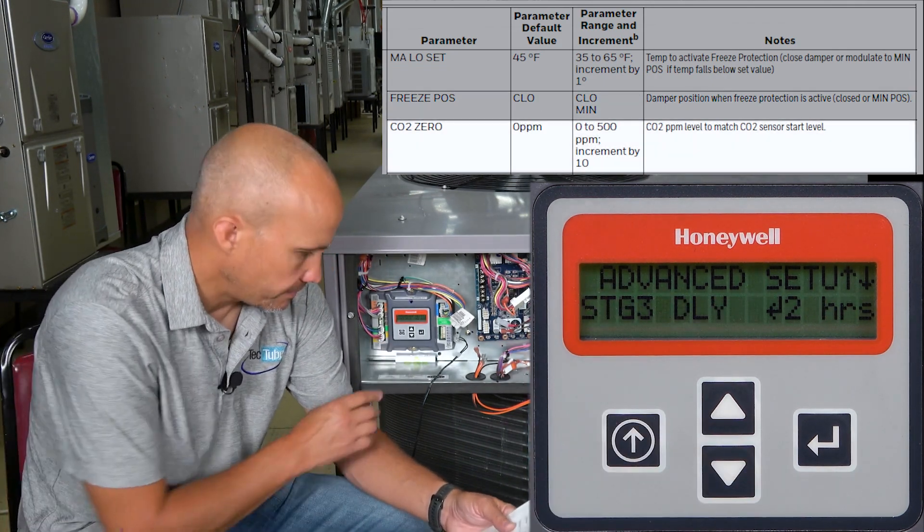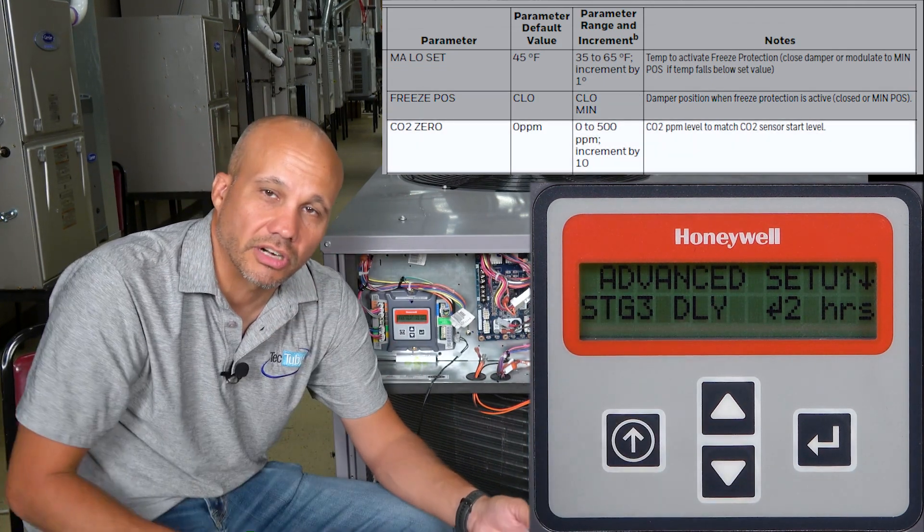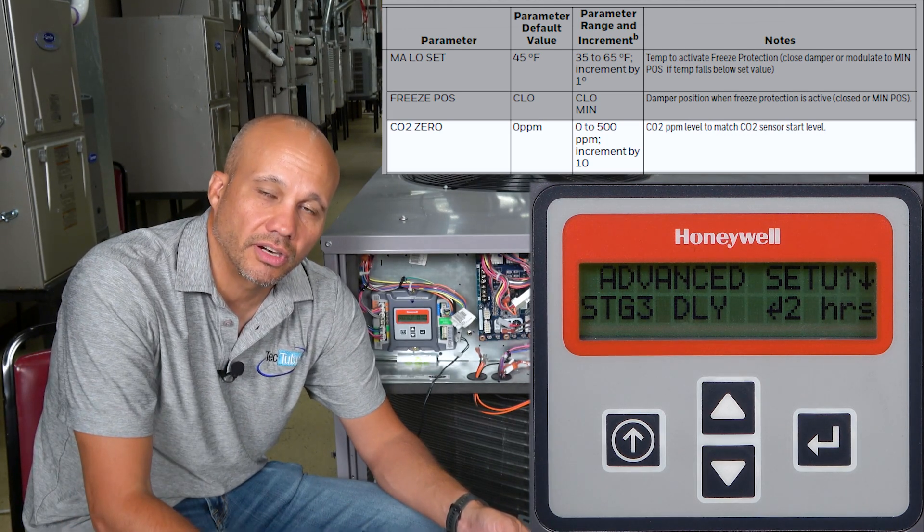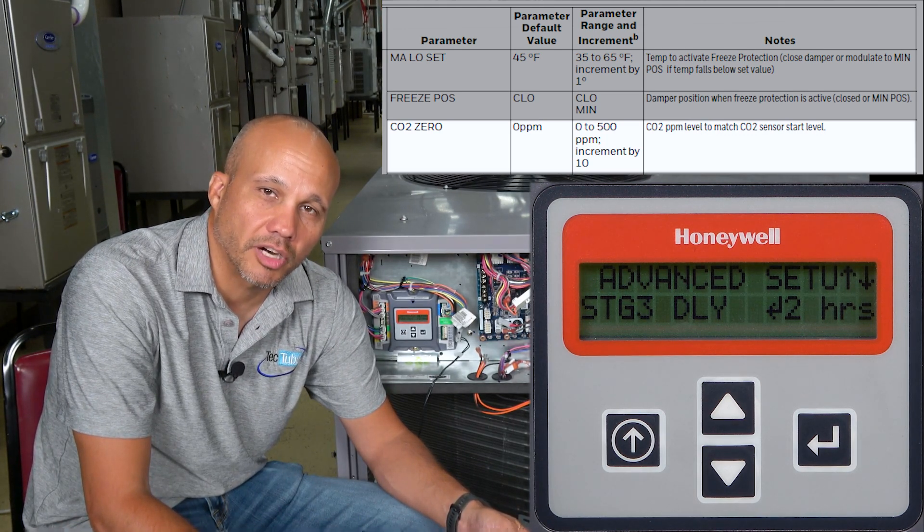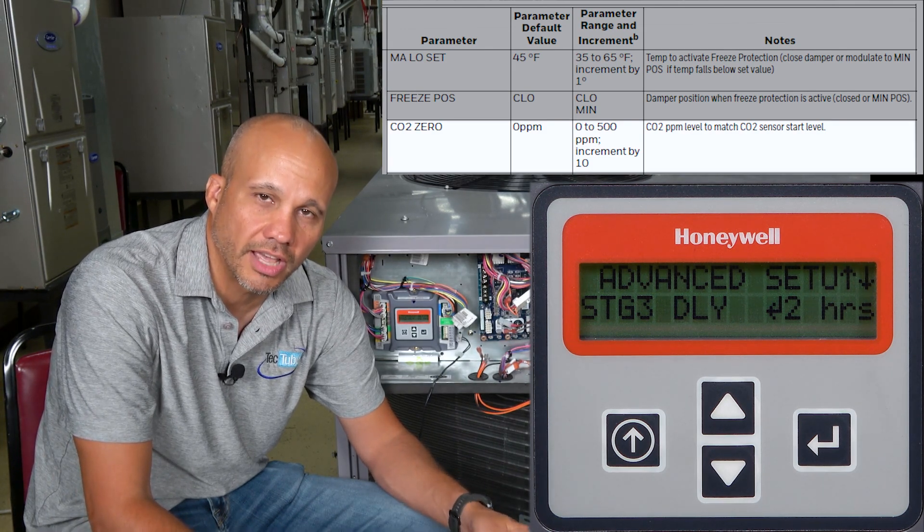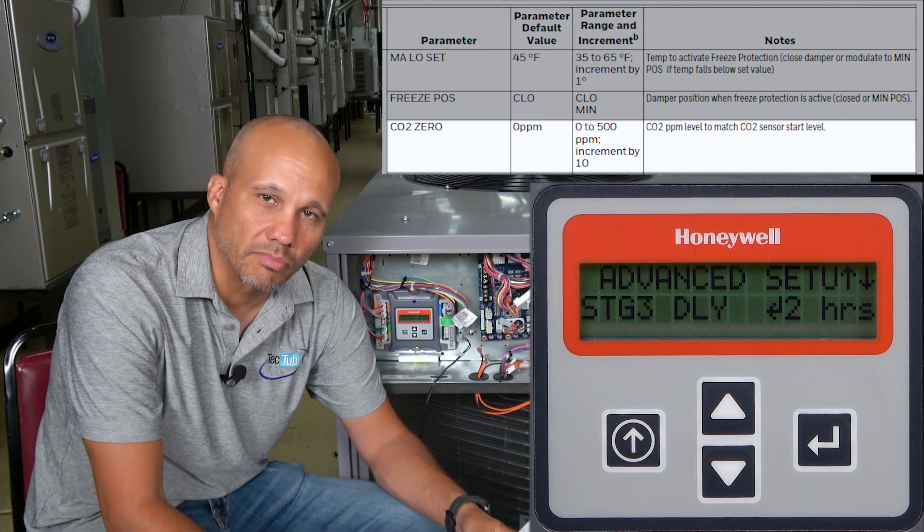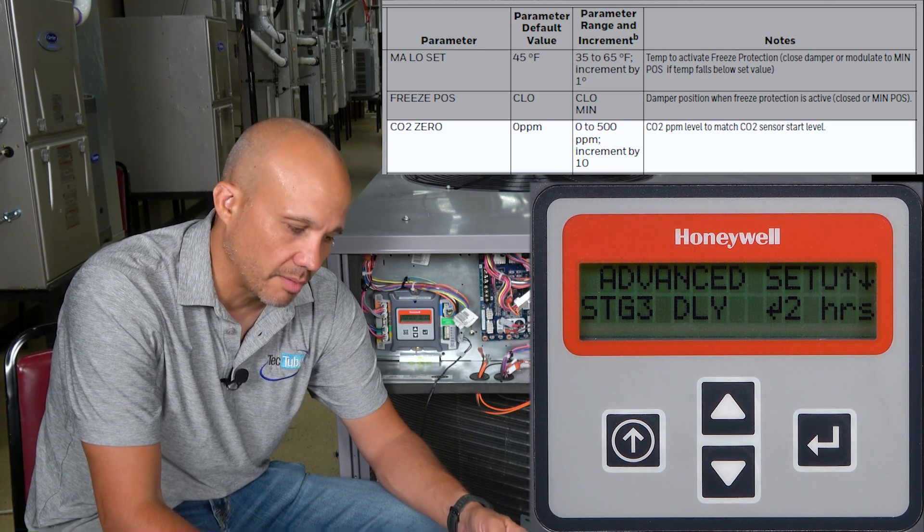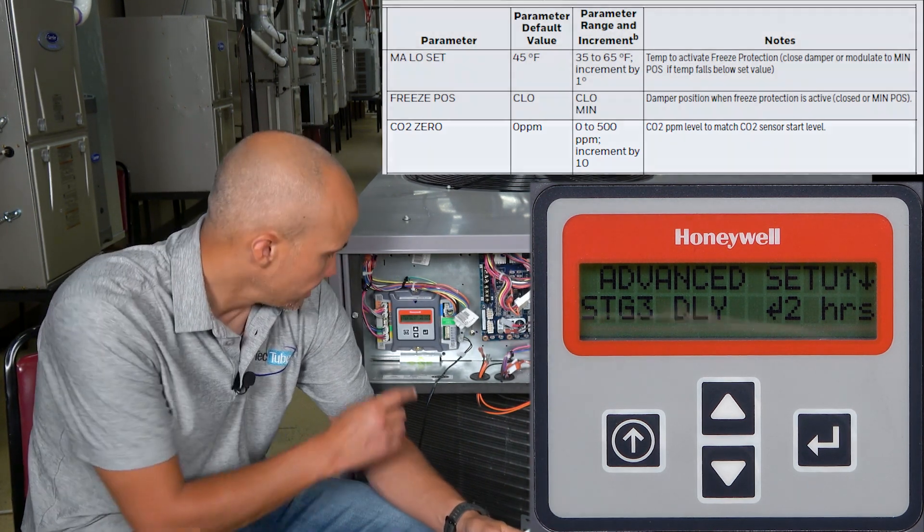The CO2 sensor - I don't have one on the screen here because I don't have one wired in. There's a zero and a span, zero to 2,000 parts per million, which is what almost every single commercial grade CO2 sensor runs at. So you would leave that alone in most applications. If you had something special you bought, then you might come in here and change that.